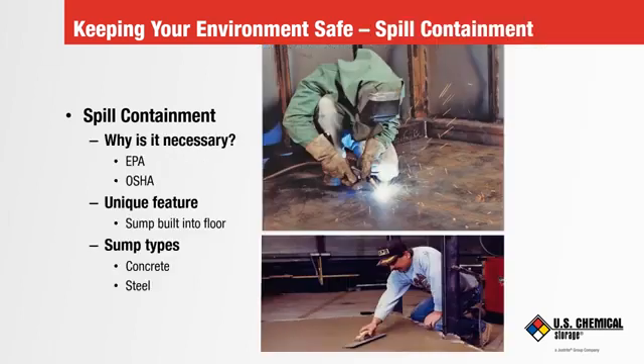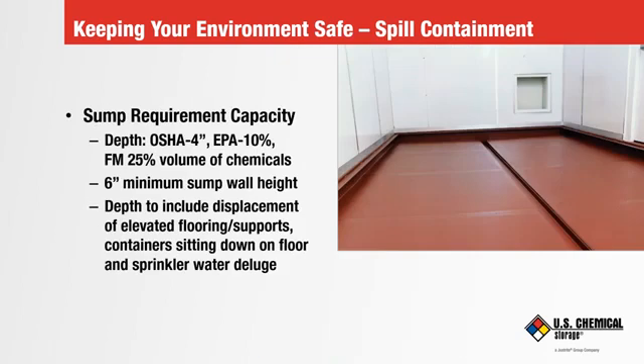Keeping your environment safe via spill containment. A chemical storage building's most unique feature is that it must have a liquid-tight sump built into the floor. Sumps are constructed of either a continuously poured concrete curb integral to the concrete floor or a continuous welded 10-gauge steel plate for sump walls and floor. Next slide. The idea is to catch spills and keep them from getting into the soil under and or around the building.